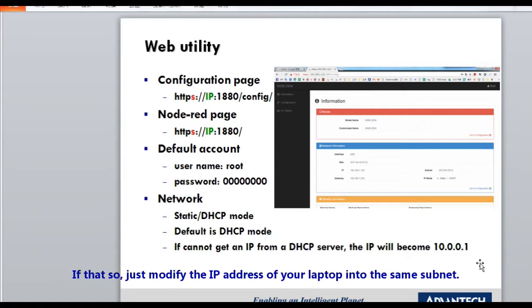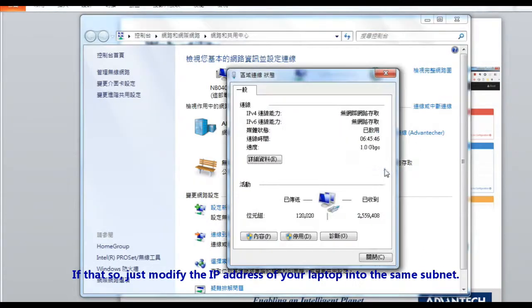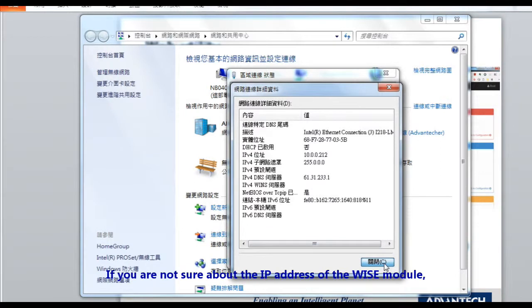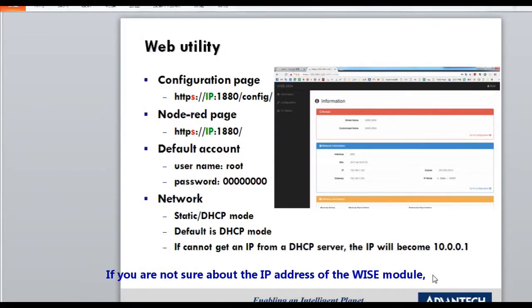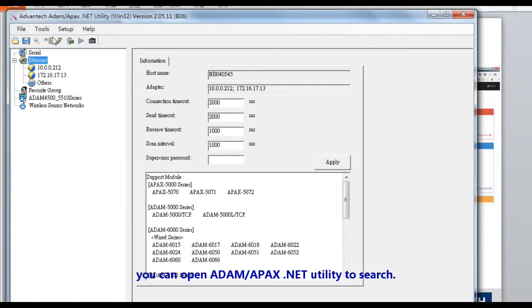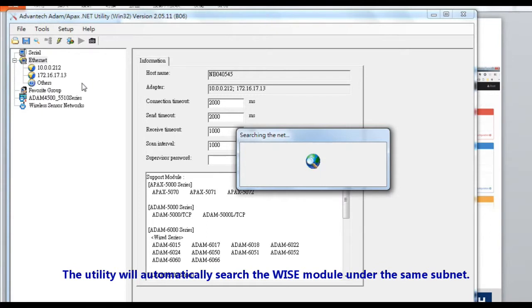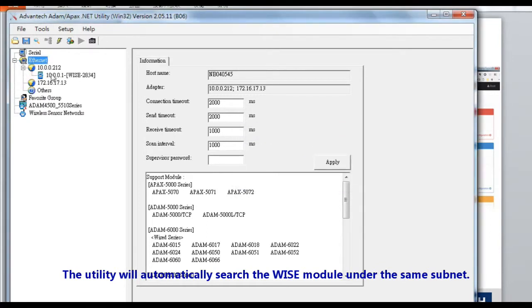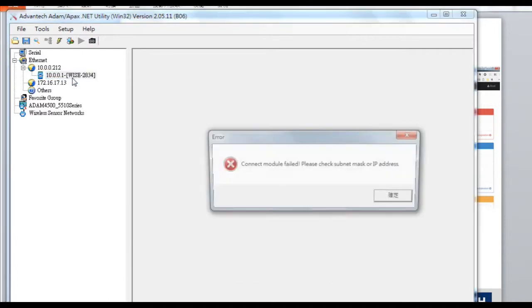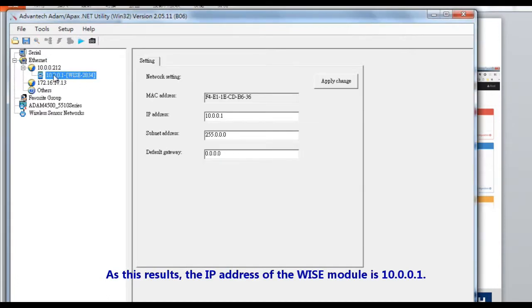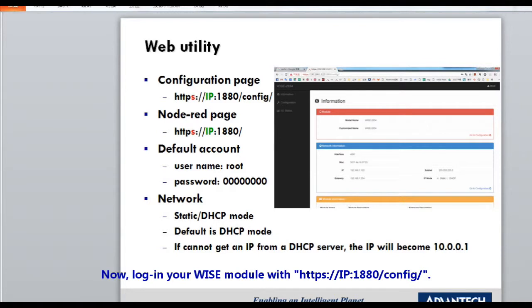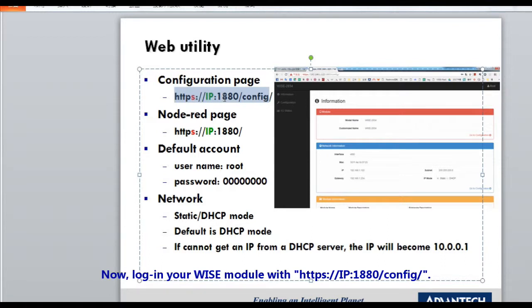If that's the case, just modify your laptop's IP address to the same subnet. If you are unsure about the IP address of your WISE module, you can open the ADAM/APAX.NET utility to search — it will automatically find the WISE module on the same subnet. In this result, the IP address of the WISE module is 10.0.0.1. Now log in to the WISE module at HTTPS, IP address, port 1880, /config/.